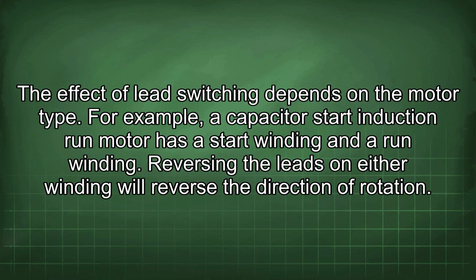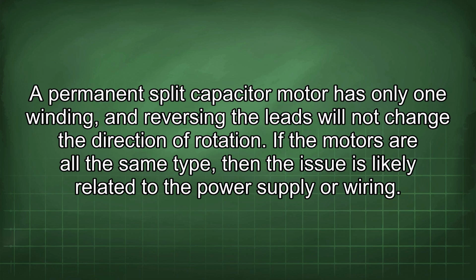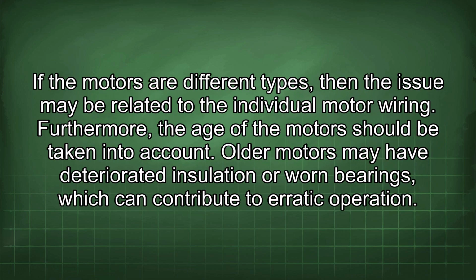Additional points to consider are the type of motor being used. The effect of lead switching depends on the motor type. For example, a capacitor start induction run motor has a start winding and a run winding. Reversing the leads on either winding will reverse the direction of rotation. A permanent split capacitor motor has only one winding, and reversing the leads will not change the direction of rotation. If the motors are all the same type, then the issue is likely related to the power supply or wiring. If the motors are different types, then the issue may be related to the individual motor wiring.